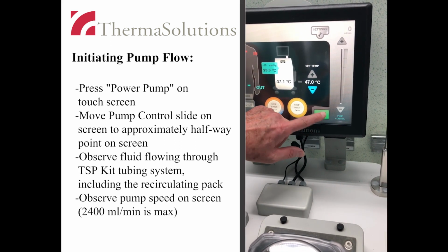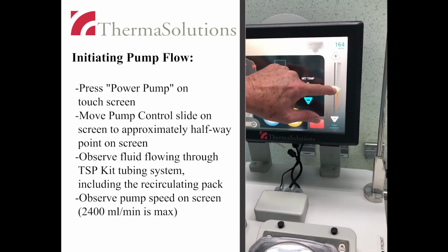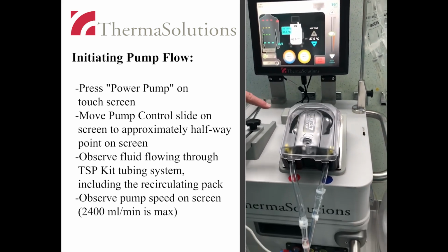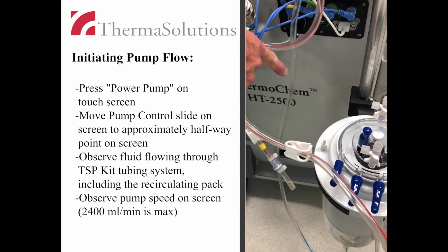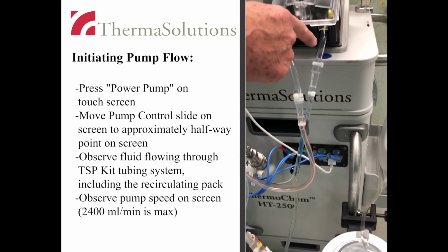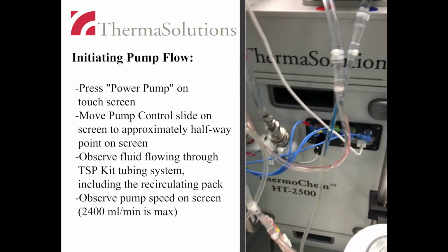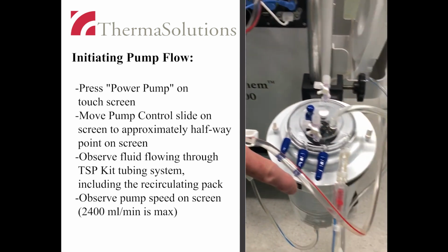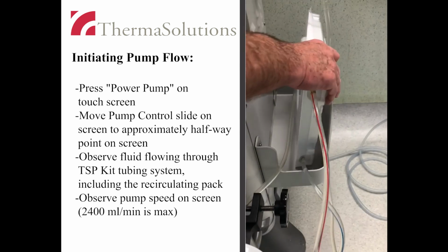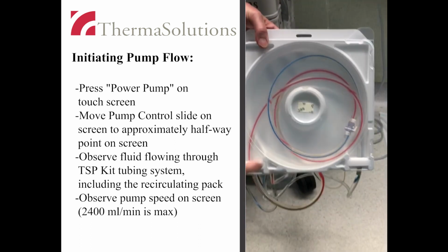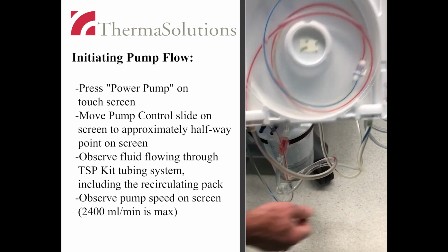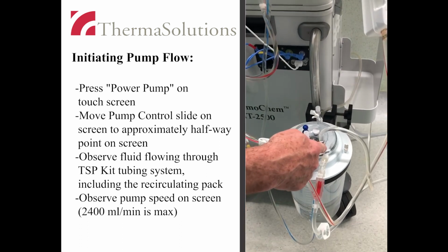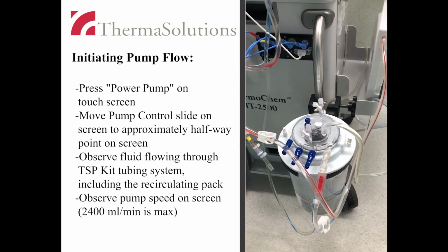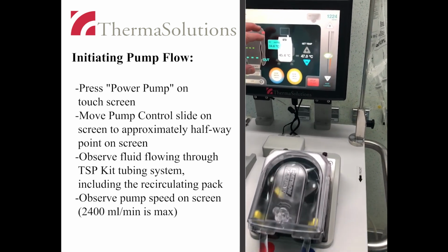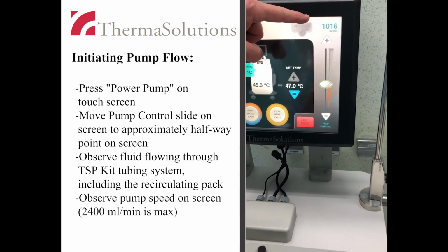Initiate pump flow for the perfusate in the TSP procedure kit by touching the power pump icon on the home screen. Move the pump control slide approximately halfway. Check the disposable tubing system for leaks and ensure all clamps and caps have been securely closed. Observe fluid flowing through the TSP kit tubing system, including the recirculating pack. Observe the pump speed on screen. 2,400 milliliters per minute is the maximum.